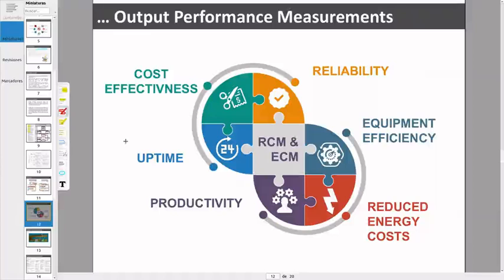Now people wonder how increasing the maintenance time can save cost. Preventive maintenance for an air handling unit will take around 1.5 to 2 hours to do a proper full overall maintenance. An energy-centered maintenance task will add approximately 30 to 45 minutes. So now our maintenance time, instead of being 2 hours, is around 3 hours.